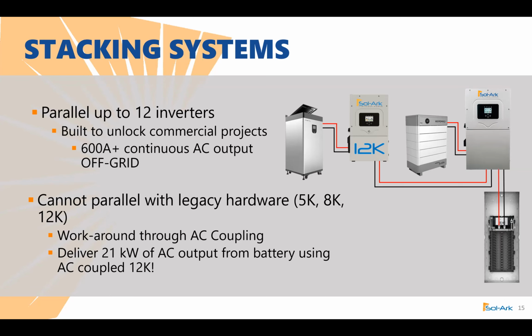But you cannot parallel with our legacy hardware. So if you are stocking some of our very old equipment, maybe I believe plus 2 years ago, we had an indoor rated model that it cannot communicate with. That's typically out of the market. Most of our stocking distributors are not going to have it anymore, but it is something to look out for. Sometimes there's a distributor holding onto a unit that's far older than we expect, and they'll try to parallel it with the new unit. Unfortunately, all our products have been changed since October of 2020, which is going to be our outdoor rated Sol-Ark 12K. And then thereon, they're all going to connect and communicate with each other.